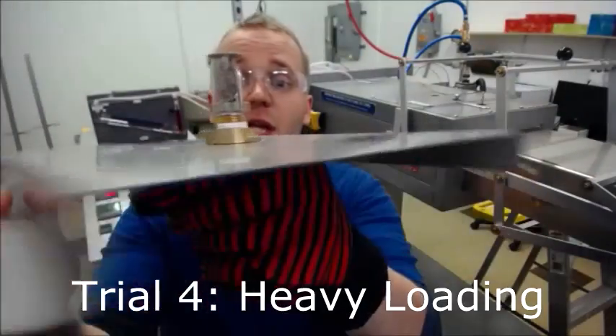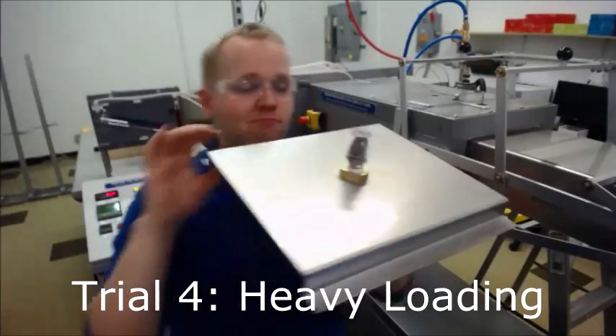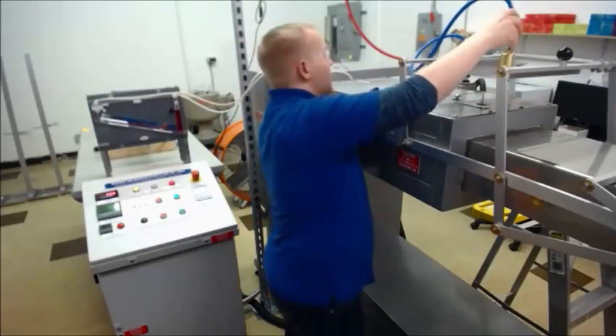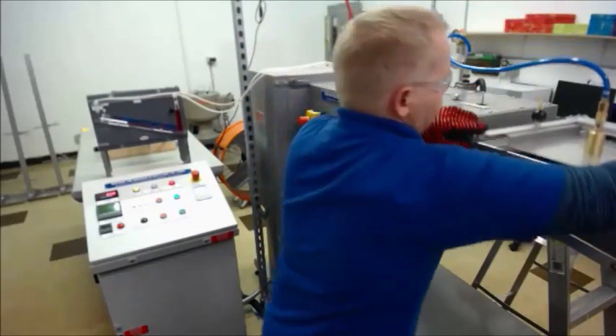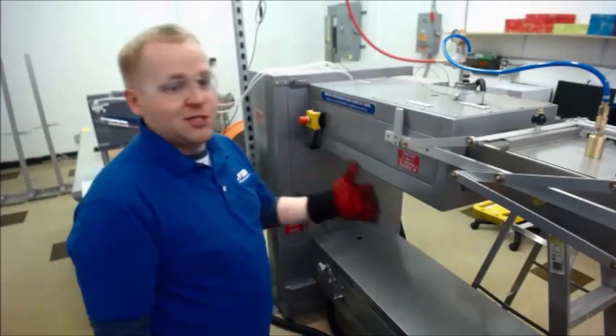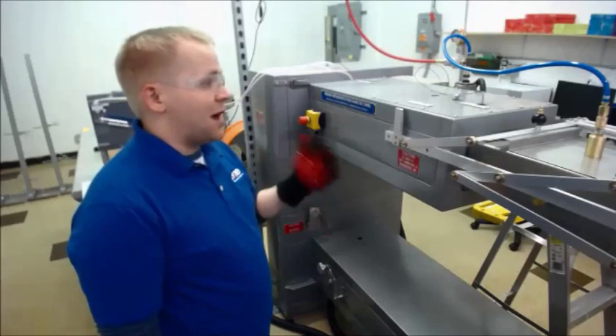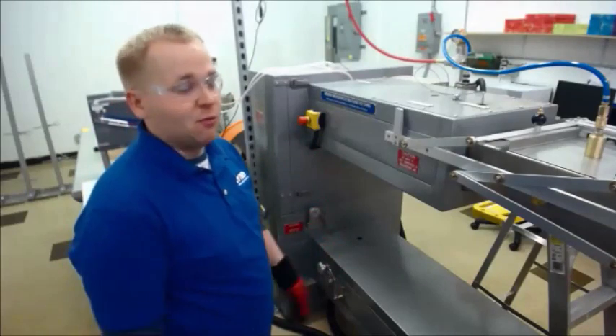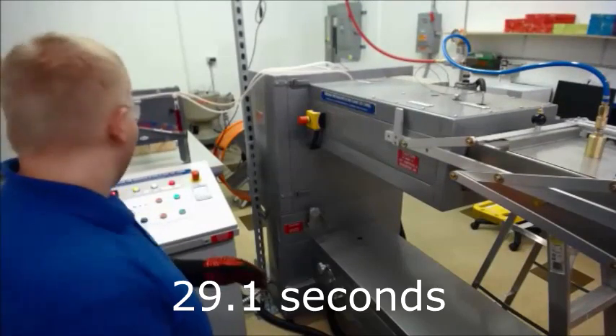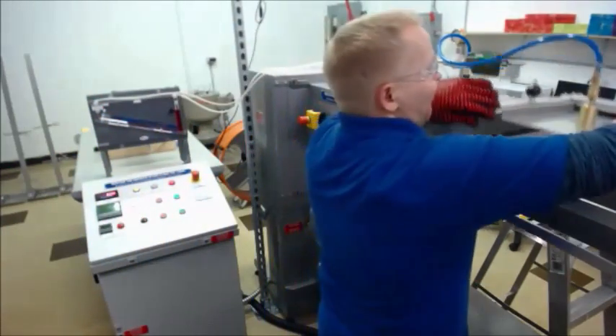Now these are pretty severely loaded. You can see there's coverage almost all around — you can see just a little bit of air might get in there. Let's see how these do. Personally, if I were looking at that, I would consider that severe and I would take the required action in the standard. Again, it is a subjective observation — is it too much loading? Does it affect performance? This one is going to fail quite a bit. 29.1 seconds — well above 17. This one is clearly affecting performance.